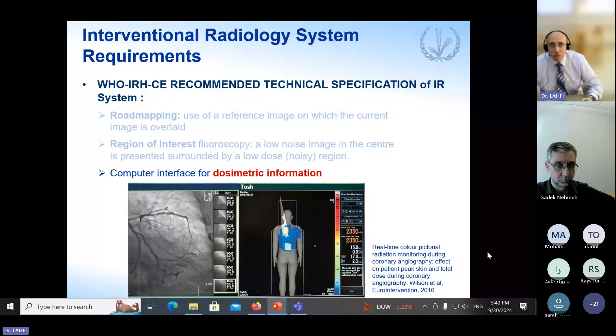We have other requirements, such as collimation without radiation with the last image hold. Also, patient positioning without the radiation, which can present a graphical display showing the central beam location, for example, and the edges of the field on the last image hold. Also, we can add automatic beam filtration. In fact, these options are now available in the majority of systems, and with time, really every day, we can see new options that serve to reduce the dose for the patient and present a clear and noiseless image during interventional radiology.